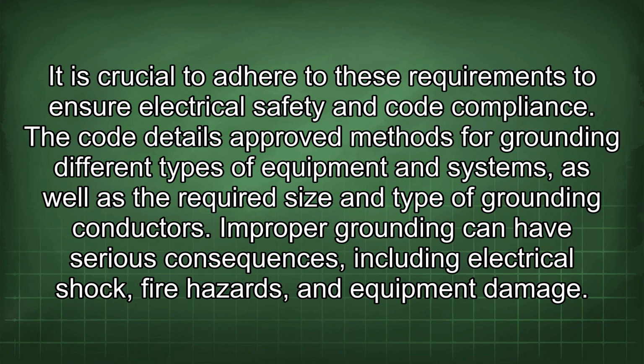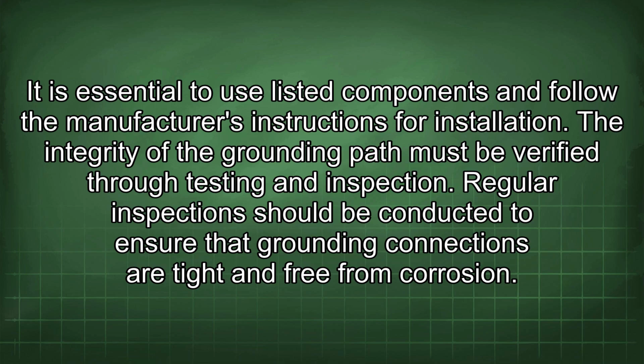The code details approved methods for grounding different types of equipment and systems, as well as the required size and type of grounding conductors. Improper grounding can have serious consequences, including electrical shock, fire hazards, and equipment damage. It is essential to use listed components and follow the manufacturer's instructions for installation. The integrity of the grounding path must be verified through testing and inspection. Regular inspections should be conducted to ensure that grounding connections are tight and free from corrosion.